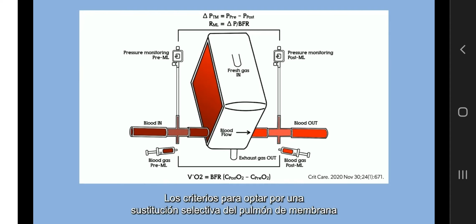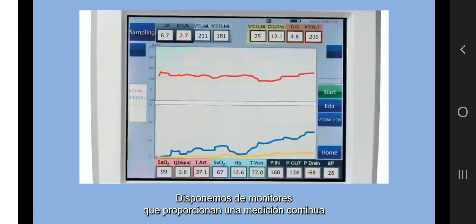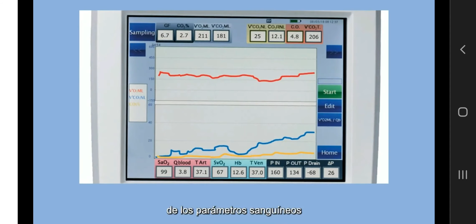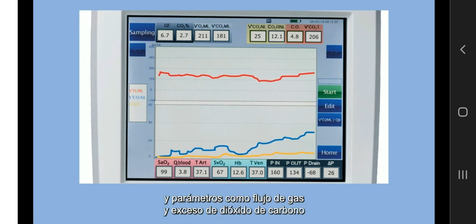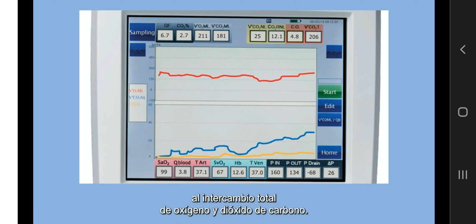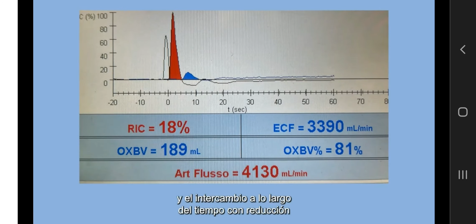You could sample pre- and post-membrane lung blood gases to evaluate performance in terms of both carbon dioxide removal and oxygen transfer. Monitors providing a continuous measurement of blood parameters, such as pre- and post-membrane lung oxygen saturation, and parameters such as sweep gas flow and carbon dioxide in the exhaust gas leaving the membrane lung, are available, also providing advanced data on the membrane lung contribution to total oxygen and carbon dioxide exchange. Other devices estimating the membrane lung effective blood volume and its change over time, with a reduction possibly linked to thrombosis, also exist.